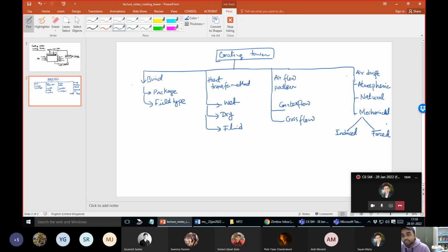So you cannot afford to have this scaling or increase of the dissolved solids present in the water beyond a certain threshold. Generally, these waters are underground water or river water. So they do have a certain extent of dissolved solid materials in them, right? It could be some chloride, some hardness chemicals, or some other compounds. And they will get concentrated due to this evaporation, right? So that is one issue with the wet type towers.